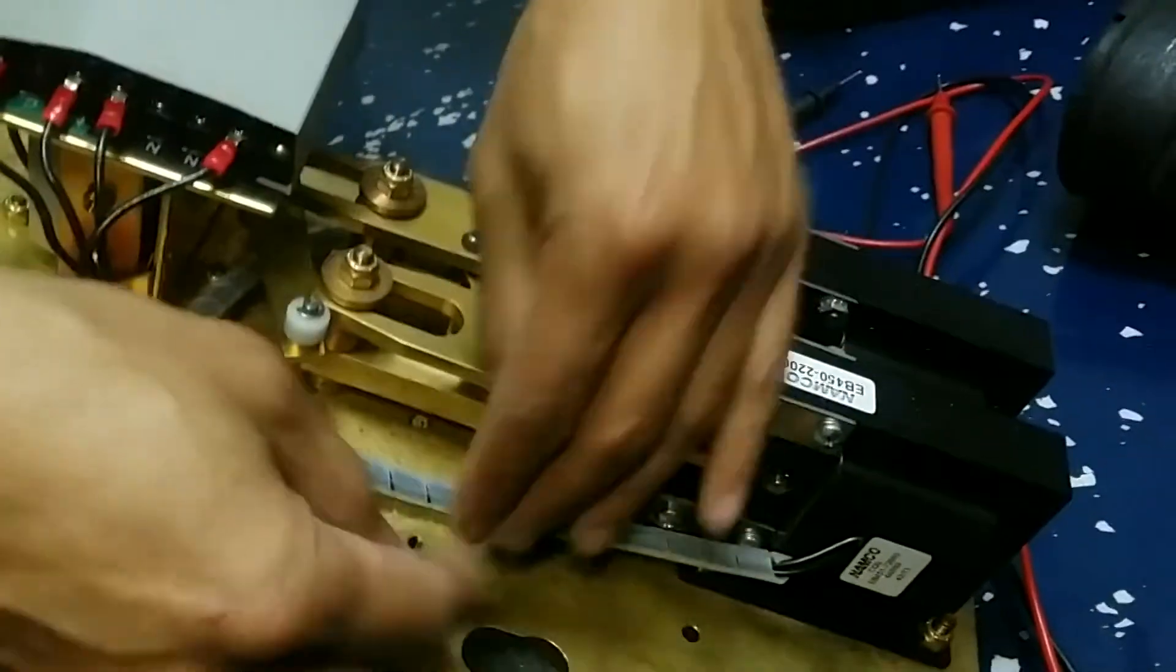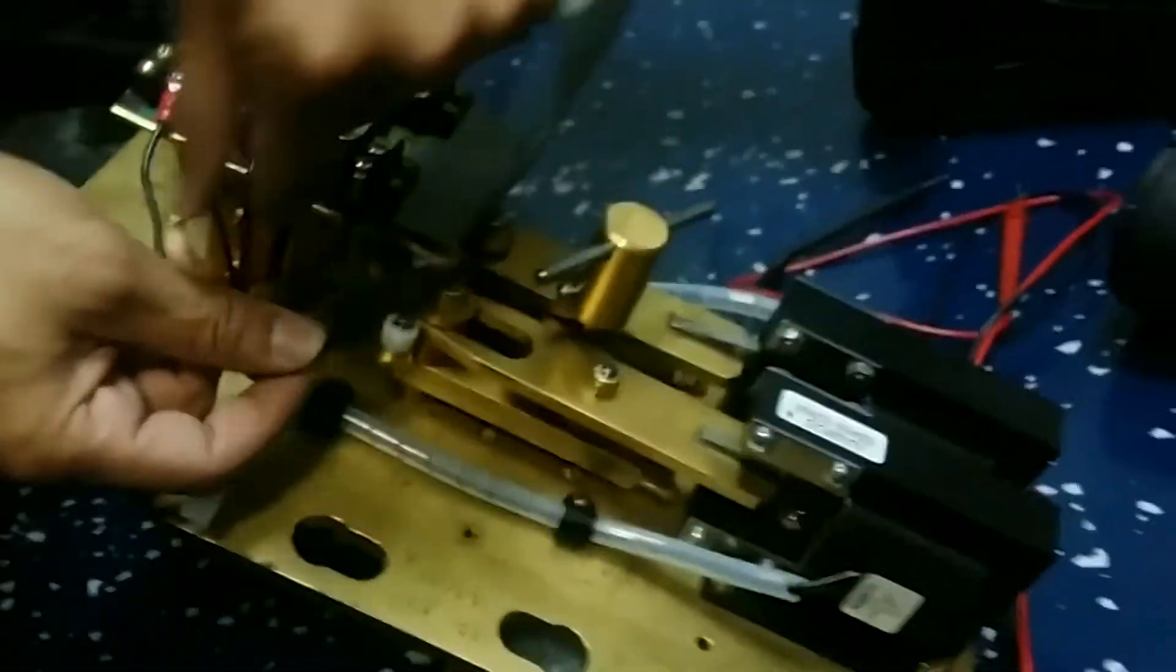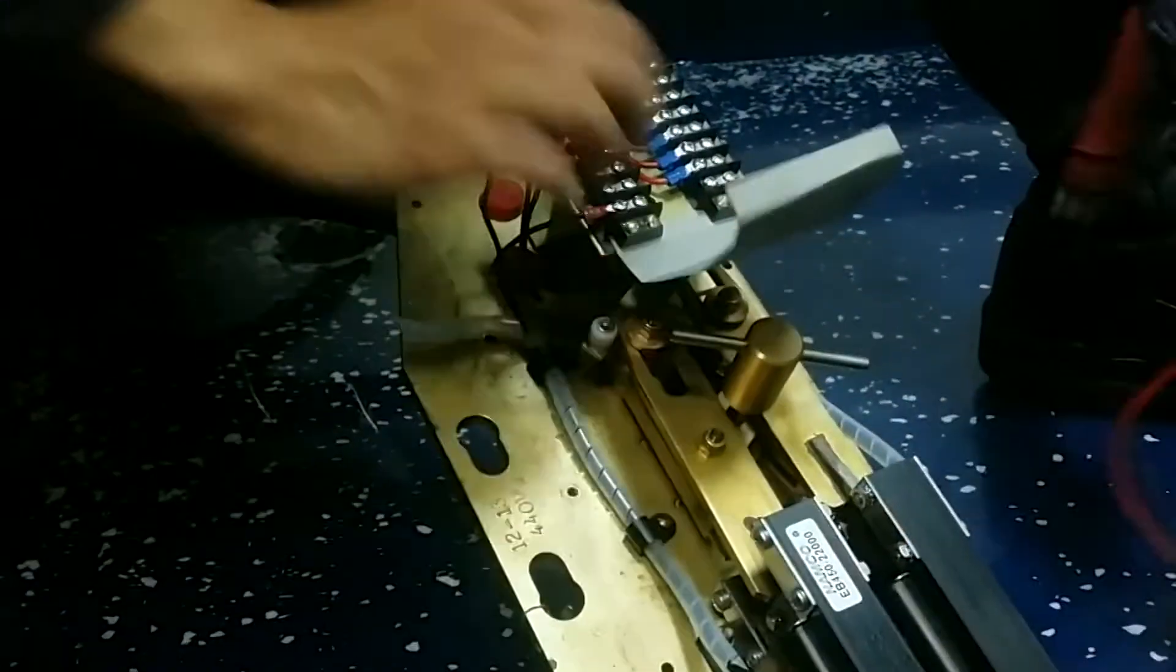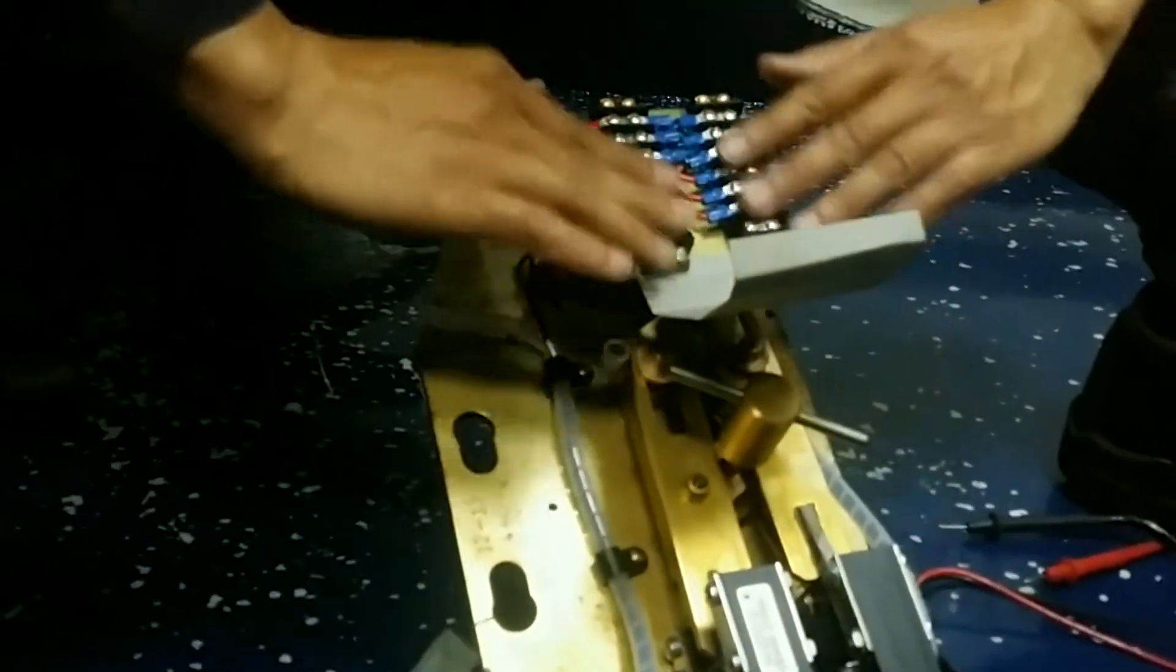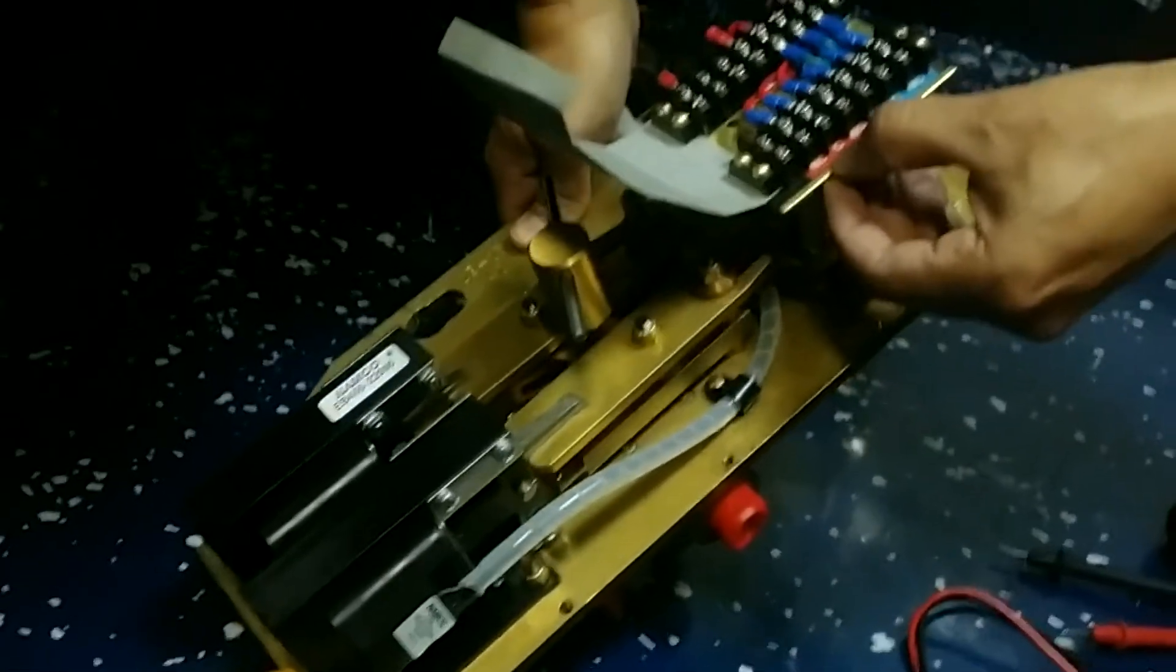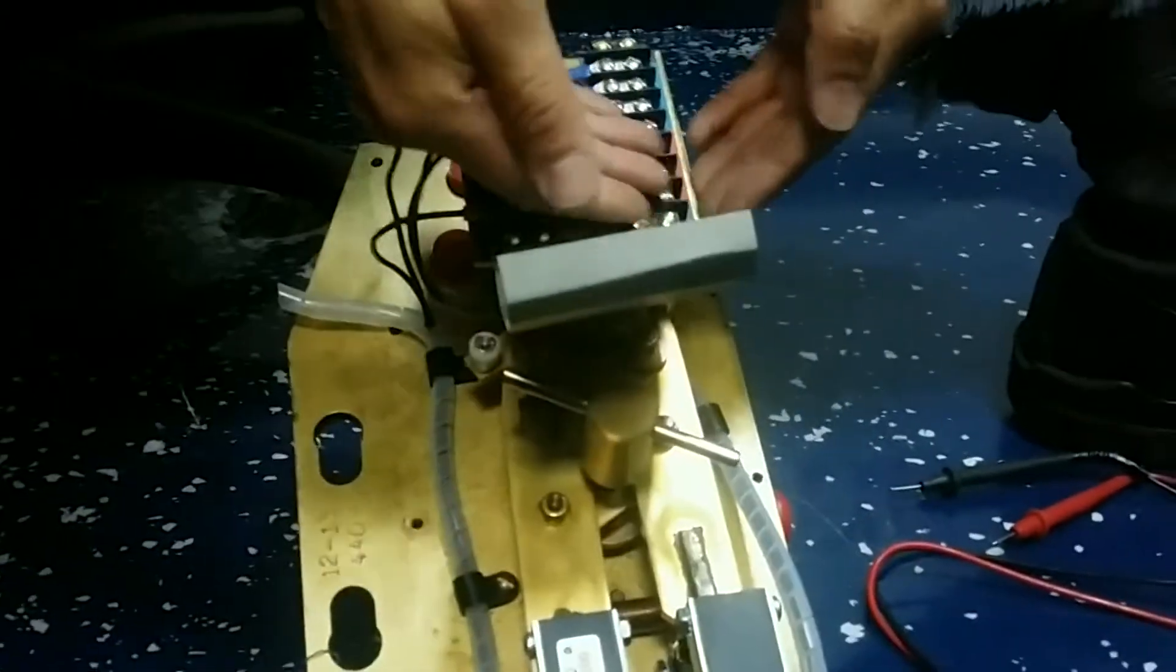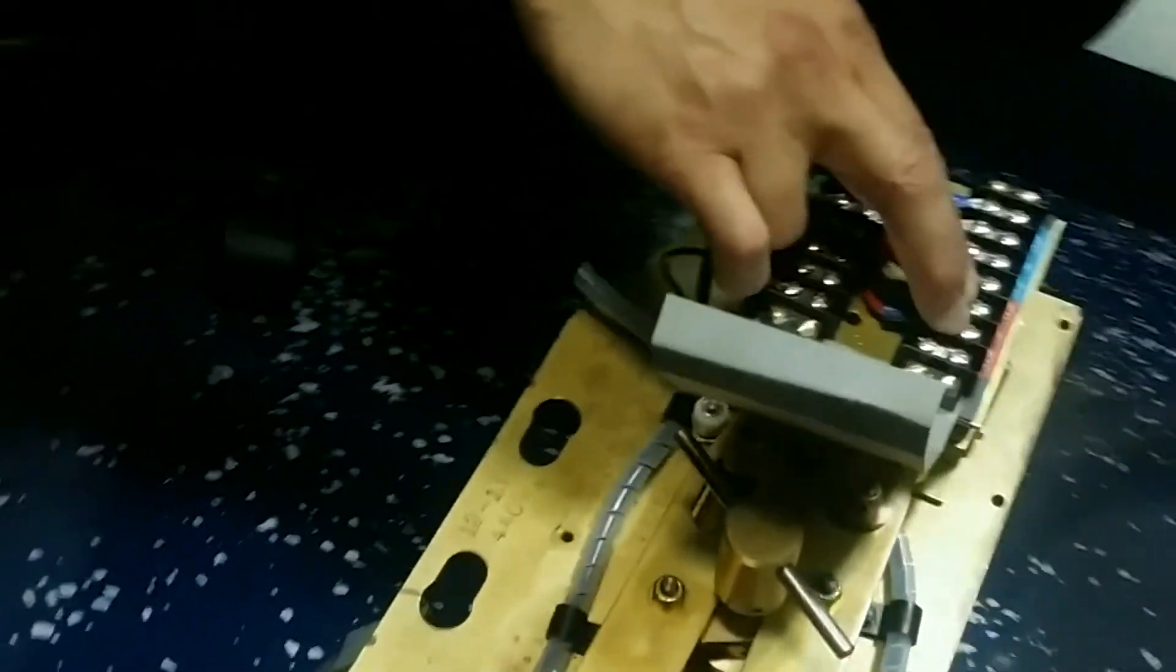Electrically, these solenoids, both of them, this is my open solenoid, and this is my closed solenoid. My open solenoid, if you follow the wires, there is one, and then these two wires belong to my open solenoid, so therefore, these other two wires belong to my closed solenoid. Very important to note is that we got switches, the microswitches are actually located inside there, and all of these wires are connected into this terminal board for easier connections. We got three sections of microswitches, so that is why the normally closed, the common, and the open, that is the red, the blue, and the green ones, and it's just for easy identification. These ones are for auxiliary components. As a matter of fact, today we'll be wiring these two here, so that we will command the AFFF pump to start when the valve is shifted from closed to open.